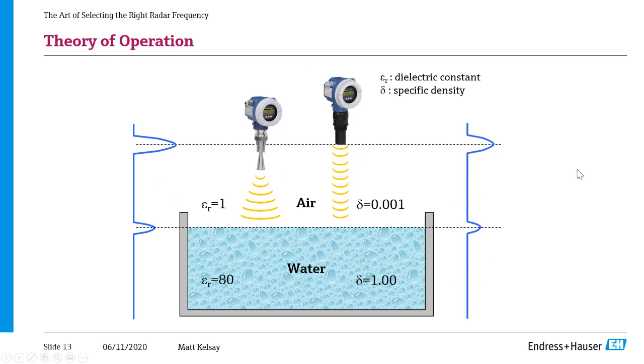So on the right, you can now see an ultrasonic device, and for water, it looks very, very similar. The reason is that air and water have a big density difference. So you get that same type of signal launch, the signal travels down, and you get a nice big reflection off the surface of the water. It's very easy for that ultrasonic device to pick out the level.